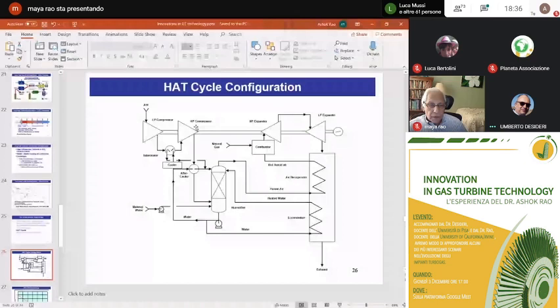Because you don't want any, in the humidifier, if you can see this diagram 26, the water is being evaporated, no doubt, but there will be some mist carry over, some droplets carry over, even if you have a very good mist eliminator. And these droplets will carry with them any salts that might be present in the water, any dissolved material. And that's why this water has to be demineralized. But again, in our evaluation, what we found is that the raw makeup water that you use upstream of the demineralizer is less than the amount of water that you use in a combined cycle as makeup to the cooling tower. I hope that answers both questions.